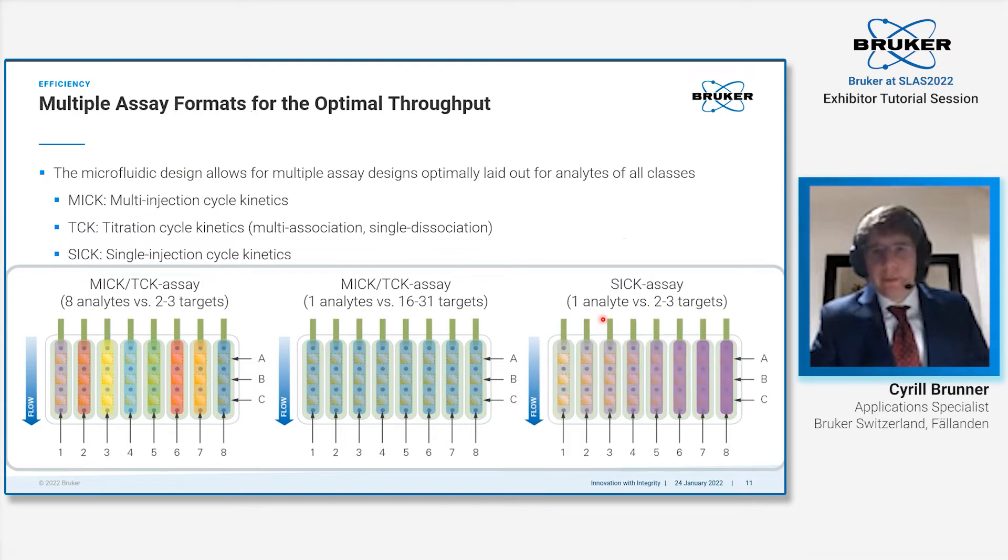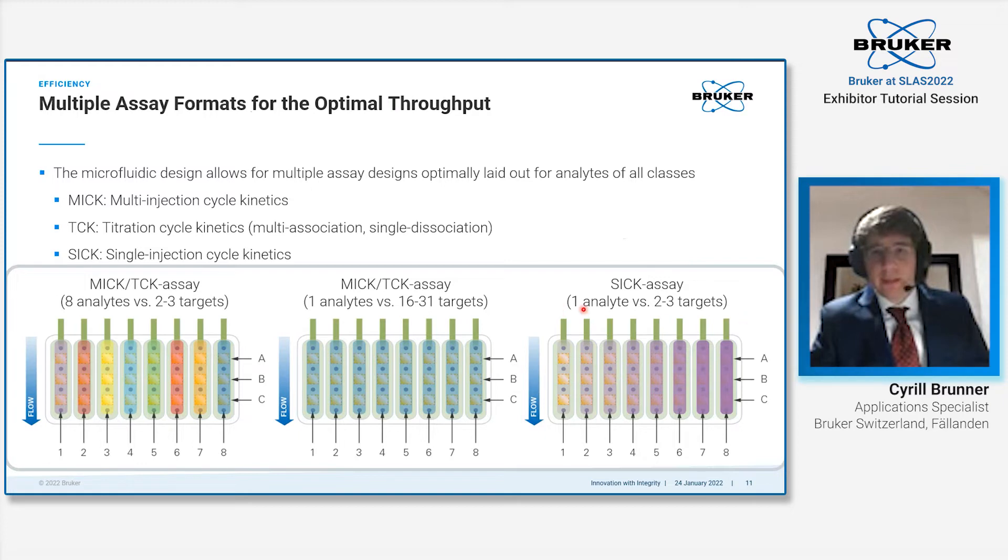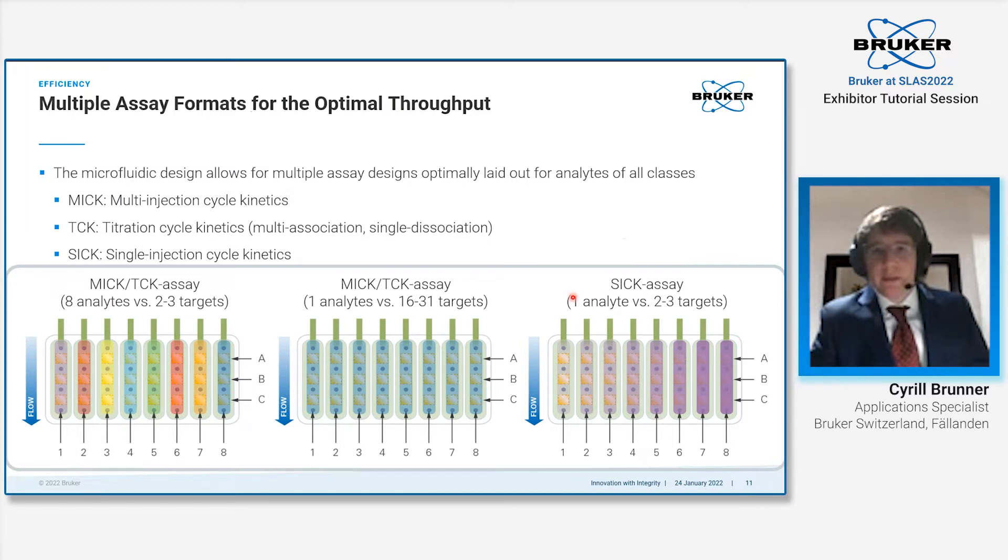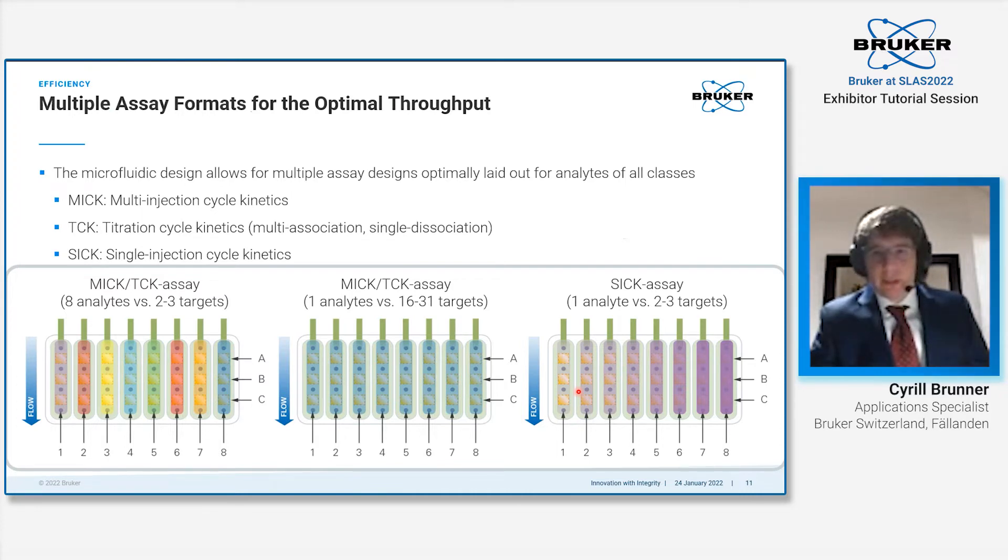Alternatively, we have the SICK assay format where you have eight flow channels, each with a different concentration. You make a dilution series over your eight flow channels, inject one analyte against two to three targets. You get within one injection two to three kinetic characterizations of the compound.